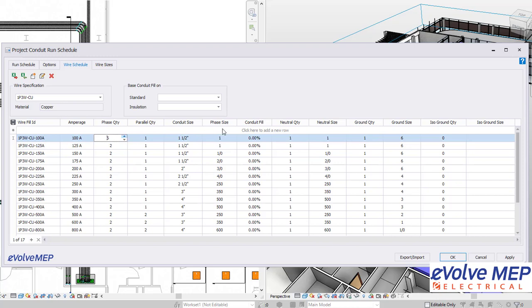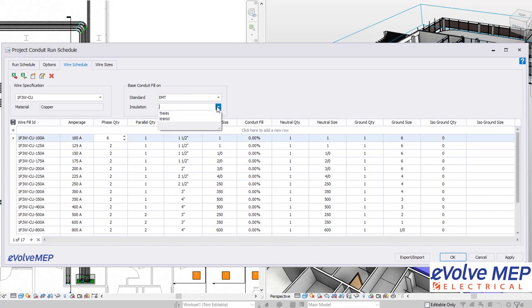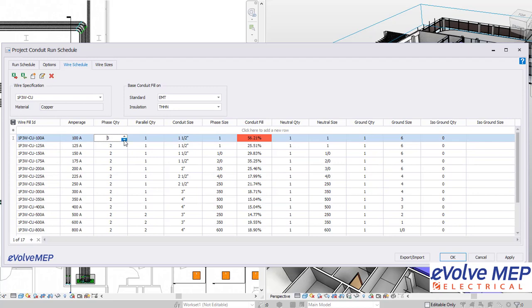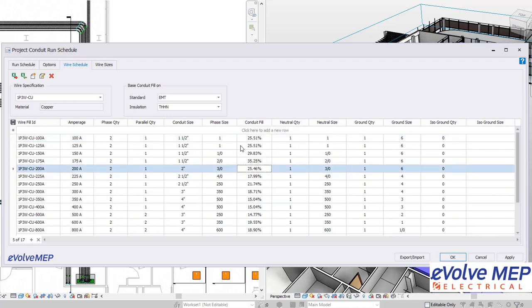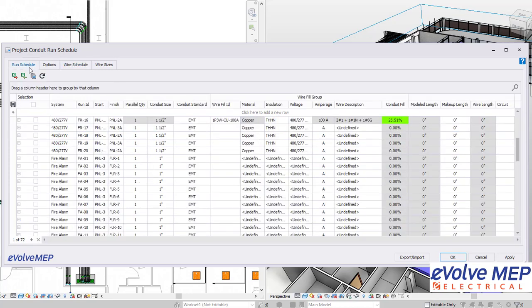All that good stuff. I'm going to bump up the phase quantity and show you what happens when you fill in right here for the base conduit fill-on. This will show you the conduit fill, and if it's exceeding, then it will turn red. I'll bump that back down to show you that it will go back to normal.